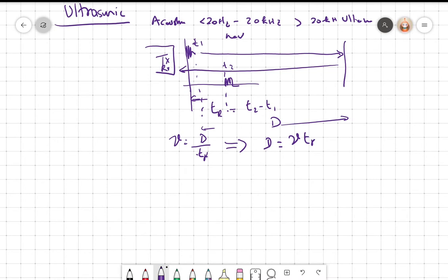You can buy it for measuring up to few hundred meters. But the one thing is that you need a reflecting surface to measure the displacement. And also there is quite a bit of error, because velocity is anywhere between 325 to 335 meters per second, depending upon the air quality, right? If air is humid, you have more velocity. If it is very dry, you have less velocity. So there is a small error in this measurement, but you can always correct it if you know the air quality and what the velocity is, and compensate for it.